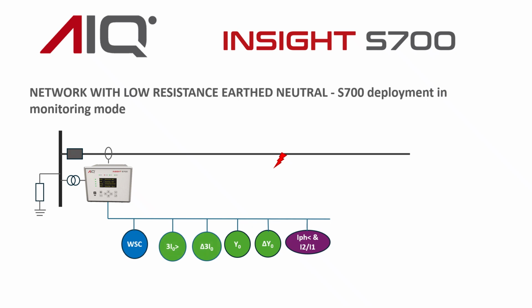For systems with resistance earth or directly earth neutral, earth fault currents will normally be sufficiently high to cause traditional protection operation. However, if high impedance earth fault is specifically targeted to be identified and not for tripping, the S700 can be deployed in monitoring mode to detect such faults.